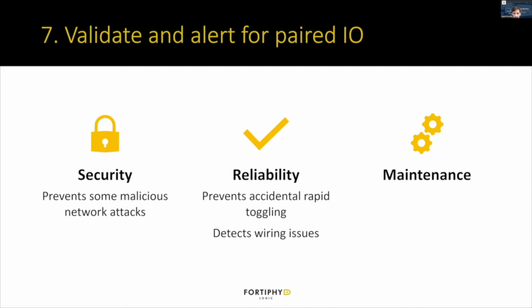Some logic is written poorly in the HMI, or maybe faulty wiring is happening that would cause rapid toggling. So having that kind of debounce, having that delay within the PLC logic, can help detect and prevent physical damage from that rapid toggling.